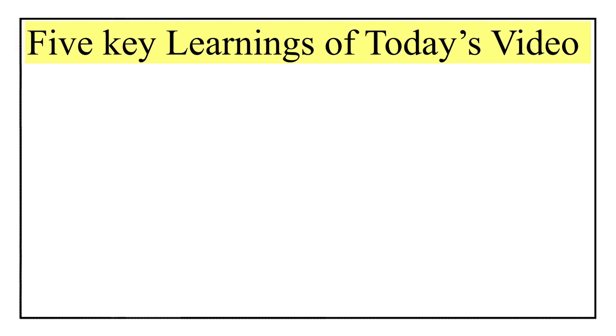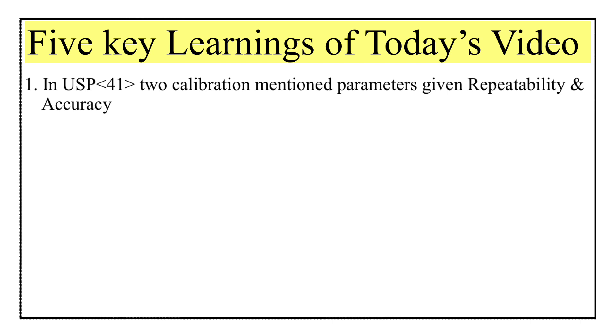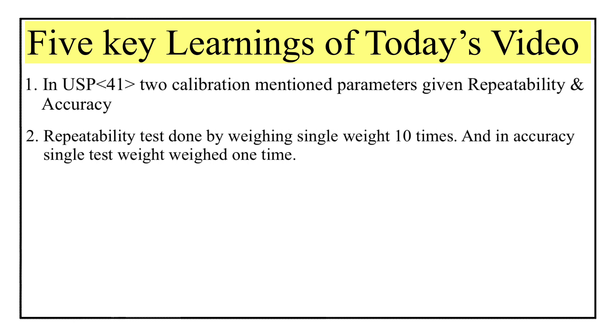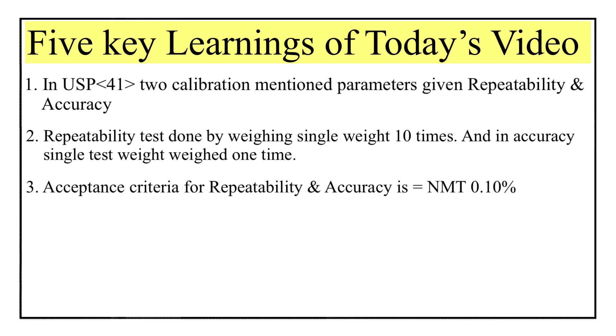Let us quickly revise what we have learned today. We learned five things related to balance calibration mentioned in USP General Chapter <41>. Point one: as per USP General Chapter <41>, there are two test parameters — repeatability and accuracy. Point two: the repeatability test is performed by weighing a single test weight 10 times and calculating standard deviation, while for the accuracy test a single test weight is weighed and the obtained value is compared with the certificate value. Point three: both repeatability and accuracy tests have an acceptance criteria of not more than 0.10 percent.